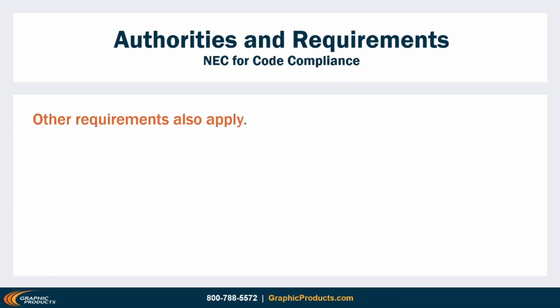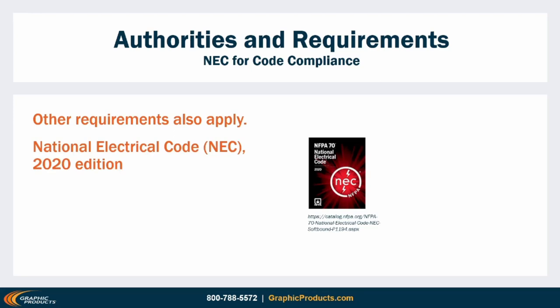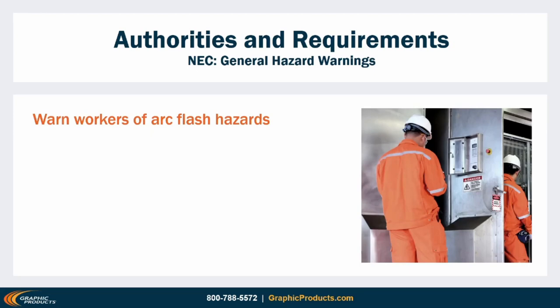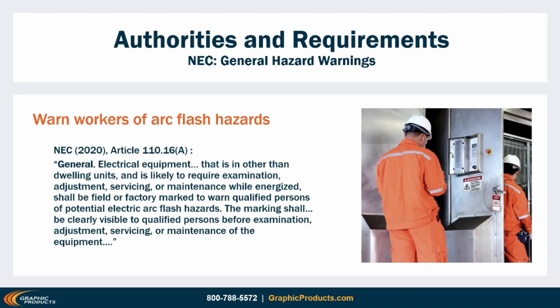OSHA focuses on safety in the workplace, but other legal requirements show up from different angles. In all 50 states, some version of the National Electrical Code, or NEC, is mandatory as part of building codes. The 2020 edition of the NEC has two requirements for arc flash labels, both found in Article 110.16. Requirement A calls for general arc flash hazard warnings: where electrical equipment likely to need examination, service, or maintenance while energized, a marking is required to warn people about the potential for arc flash. No specific details are required, but the code calls out that warnings are intended for qualified persons and must be visible before work is performed.